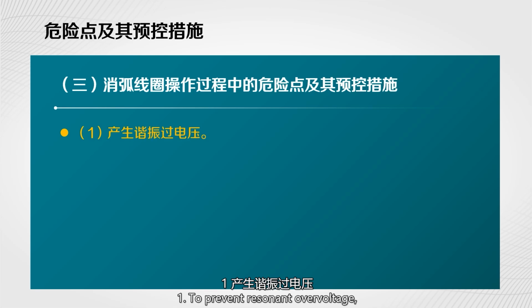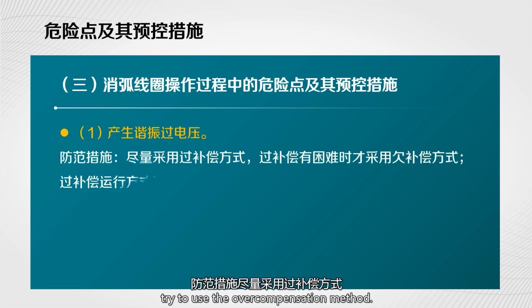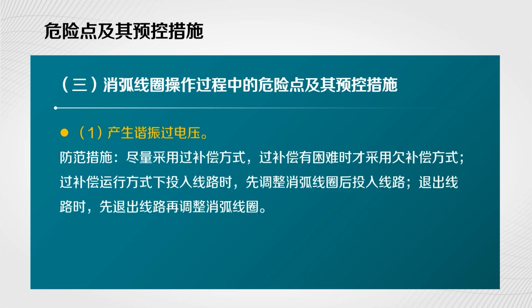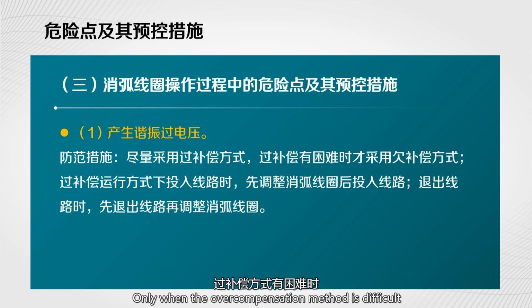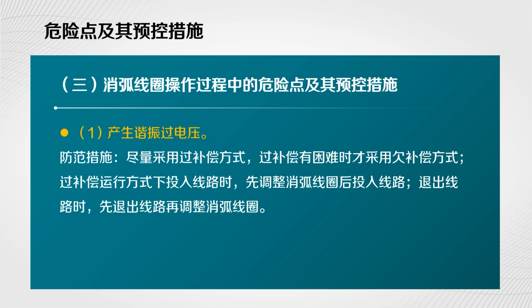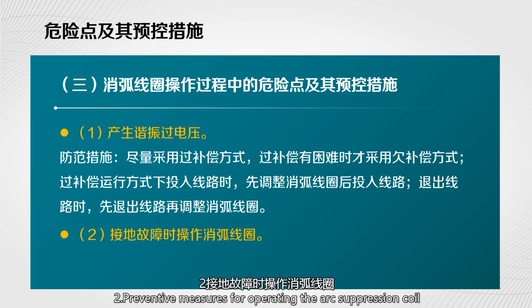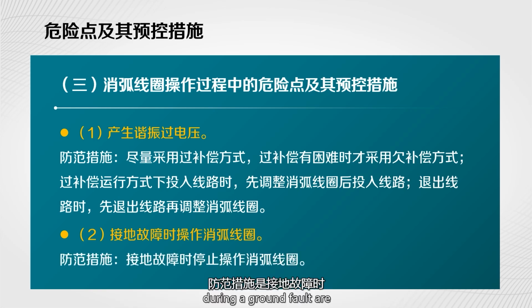Third, the dangerous points and preventive measures during the operation of the arc suppression coil. First, to prevent resonant overvoltage, try to use the overcompensation method. Only when the overcompensation method is difficult can the undercompensation method be used. When the line is put into operation in the overcompensation mode, first adjust the arc suppression coil and then put in the line. When exiting, exit the line first and then adjust the arc suppression coil. Second, the preventive measure for operating the arc suppression coil during a ground fault is to stop operating the arc suppression coil during a ground fault.